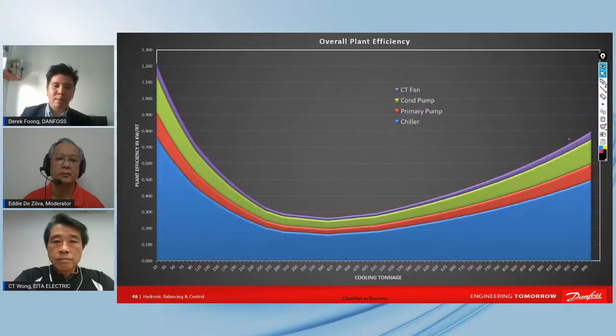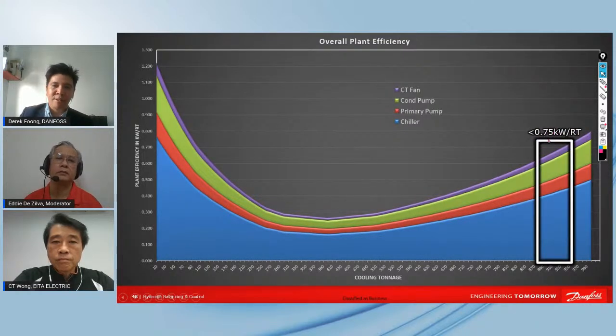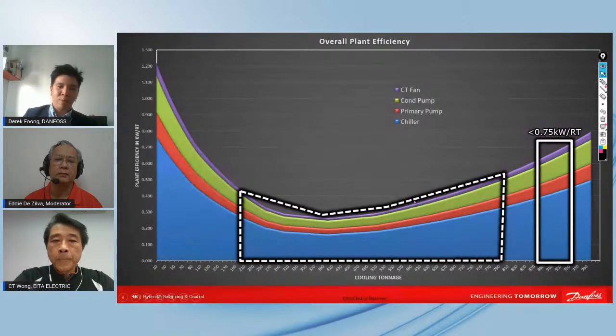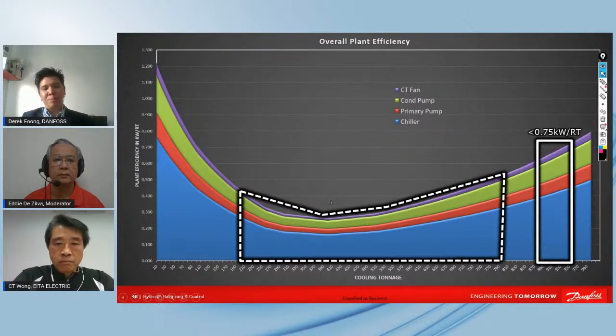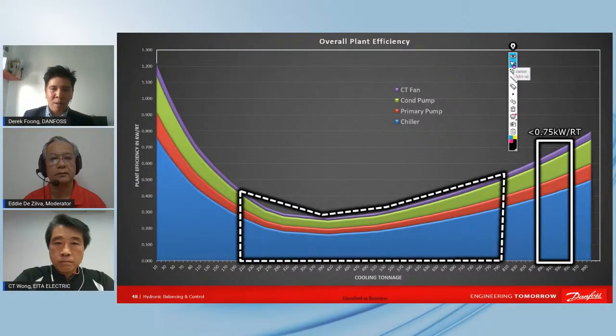When you have hydronic calculations and we size the pumps in the early stage and stack them together, we don't come up with just one bar chart and tell you, "This is the efficiency that you can achieve." Our team, with hydronic calculations, can size the pumps and the cooling towers together, and this is where we stack up. So we will be able to tell you, at part load with all the heavy equipment stacked, what the plant character is like. And this is where we define the control strategy on how we should stage the chillers on to maintain a more efficient system. So these are like the baseline set in the early stage.